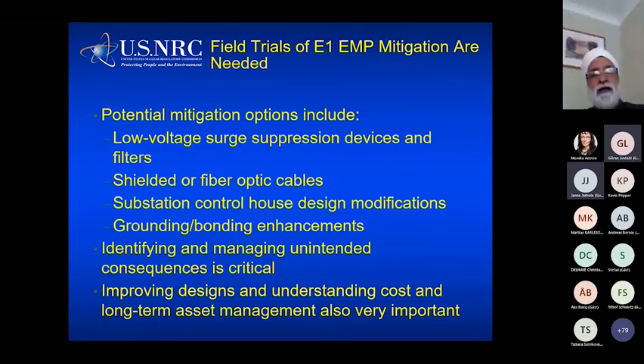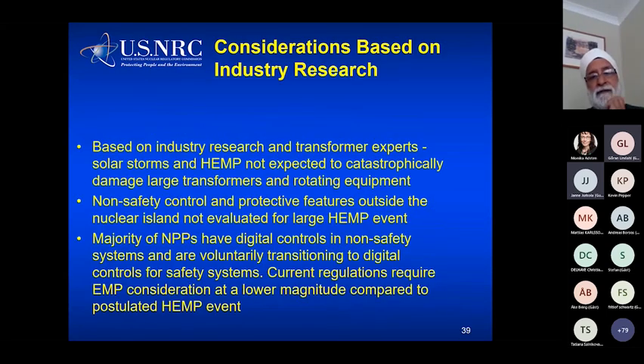So mitigation, how do we mitigate? Surge suppression devices and filters. We need shielding. We need grounding. We need better cages, as they call Faraday cages, for equipment that we feel must survive. To summarize, based on industry research and transformer experts, we do not expect a catastrophic failure of large transformers. We do expect some to fail. We do not expect all to fail. We feel the non-safety systems in the nuclear power plants need to be evaluated. We've not done that yet. And the introduction of digital controls in non-safety systems and safety systems needs to be looked at further.